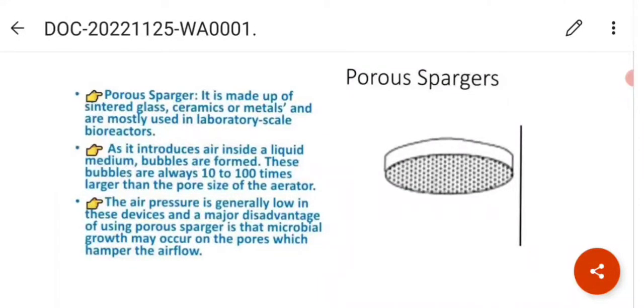We have different types of spargers. First, we have porous spargers. Porous spargers are made up of sintered glass, ceramics, or metals and are mostly found in laboratory scale bioreactors. As it introduces air inside a liquid medium, bubbles are formed. These bubbles are always 10 to 100 times larger than the pore size of the aerator. The air pressure is generally low in these devices and a major disadvantage of using porous sparger is that microbial growth may occur on the pores, which hamper the air flow.